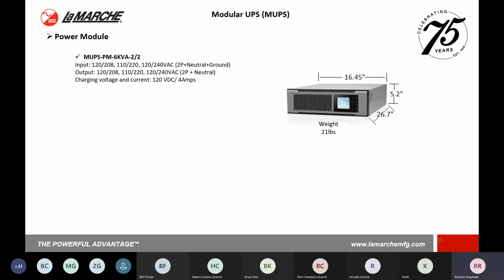Your DC bus for this specific module will be 120 volts DC and a charging current of 4 amps, and that'll be per module that you will have that charging current. So obviously adding more modules, you will increase your charging current.